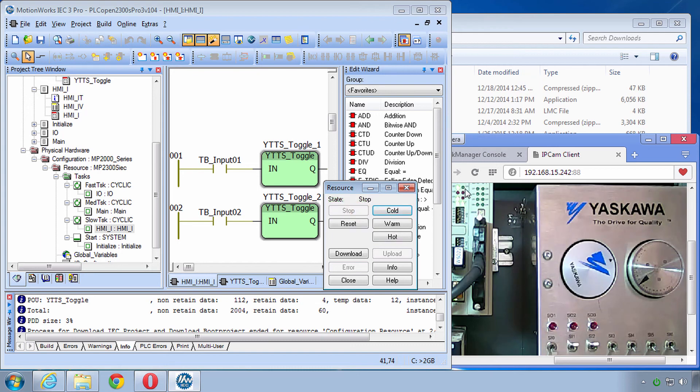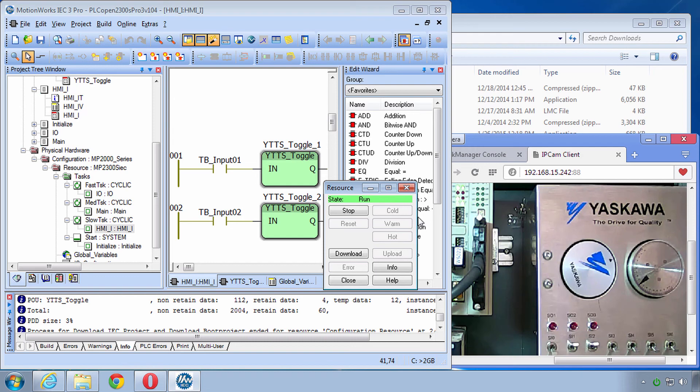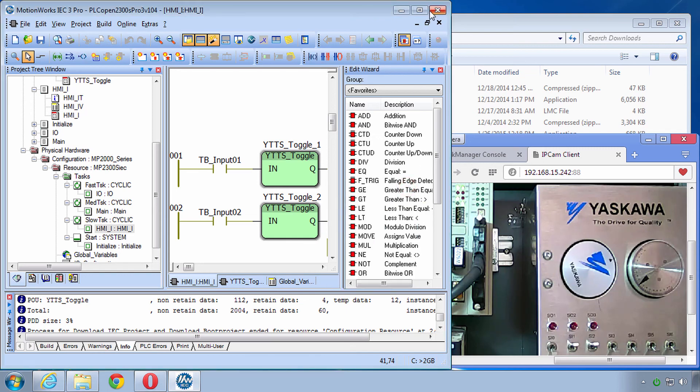And if you stop the PLC then that run light turns off. So that's a good one to keep an eye on because if this is off then you know you're not running your resource, not running your controller. So keep that one running and usually Warm Start is enough. That Cold Start may be required if the memory was cleared or if you switch projects.